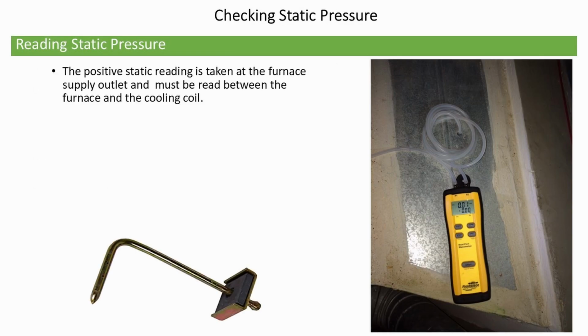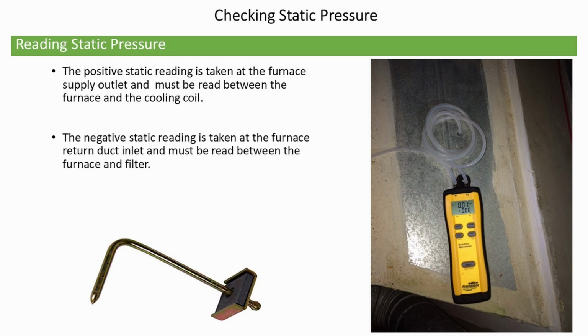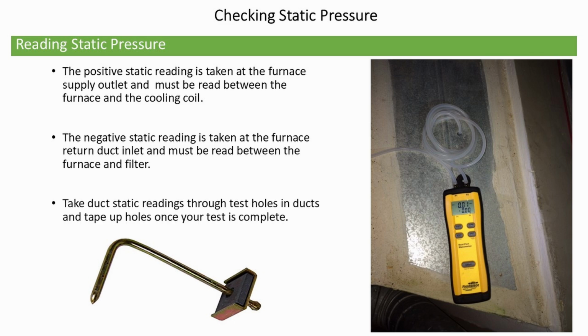Reading static pressure. The positive static reading is taken at the furnace supply outlet and must be read between the furnace and the cooling coil. The negative static pressure reading is taken at the furnace return duct inlet and must be read between the furnace and the air filter. Take the duct static readings through test holes in the duct and tape up the holes once your test is complete.